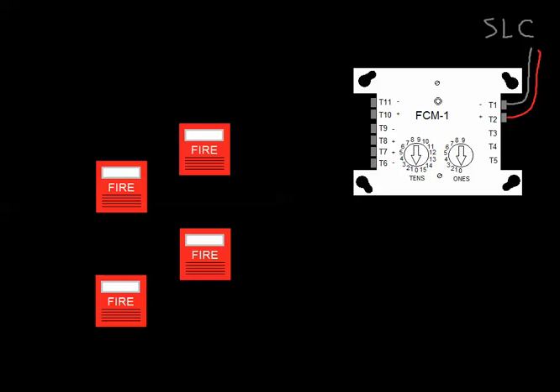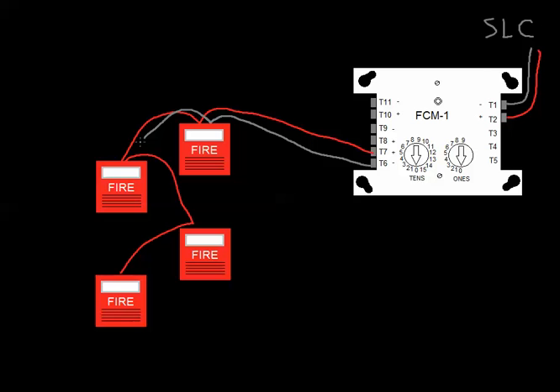So now on the output side, I'm just going to wire this up to some horn strobes, pretty much the same way that all the initiating devices have been. So I'll take a positive wire in and out of each one. As we've talked about in the past, I have to go from one to the next. I couldn't have a common terminal somewhere and then branch off to all the different devices because then it wouldn't be supervised if I cut a wire. So at the end of the circuit, I'm still going to have my resistor the same way I have all along.